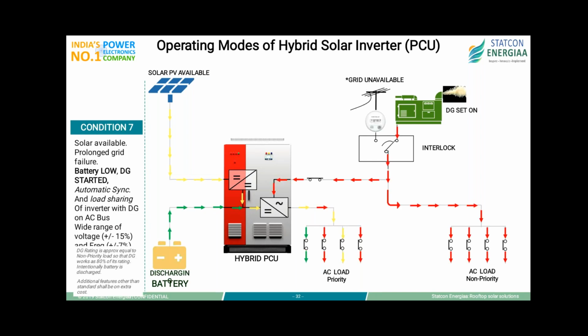This is a very interesting scenario where solar is there, battery is also there, and the DG set is there. So if you want to run certain load using a limited DG size, suppose you have a 50 kVA of load running at some instant, and your DG capacity is only 30 kVA or 25 kVA. The remaining power can be shared by PV as well as battery. Even if solar is not there, battery can take that burden. So this is a very important condition where you can reduce the DG size being used.